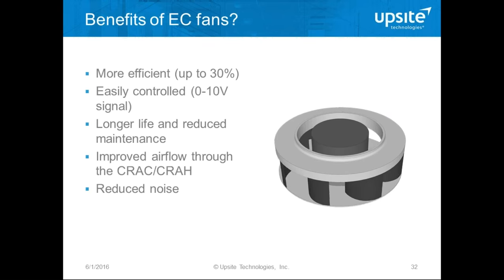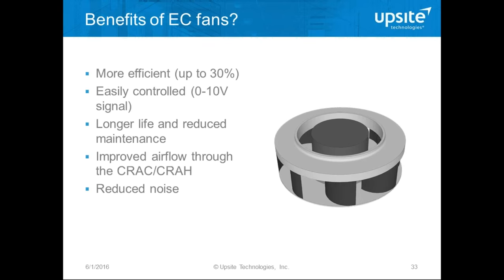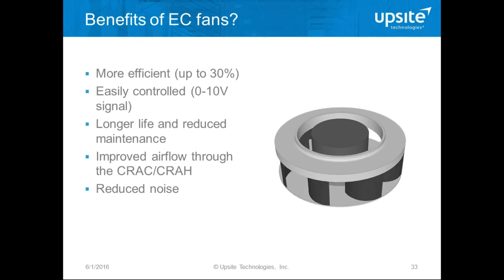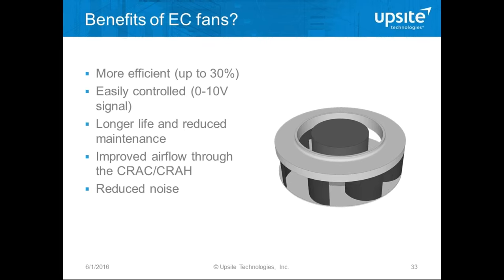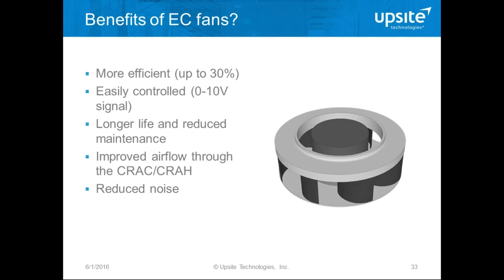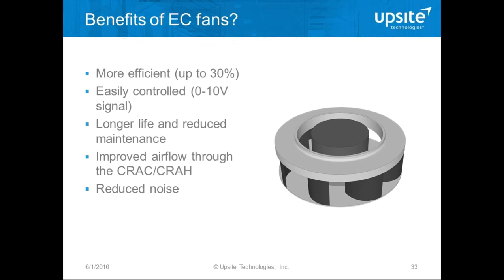Another common upgrade is to look at your cooling units and think about changing the way airflow is supplied. A common practice is to provide EC plug fans — backward curved impellers — which are much more efficient and can be controlled to give variable air volume, thereby matching cooling supply to IT airflow demand. They have a long life, reduced maintenance, can cope with higher pressure drops, and have lower noise.